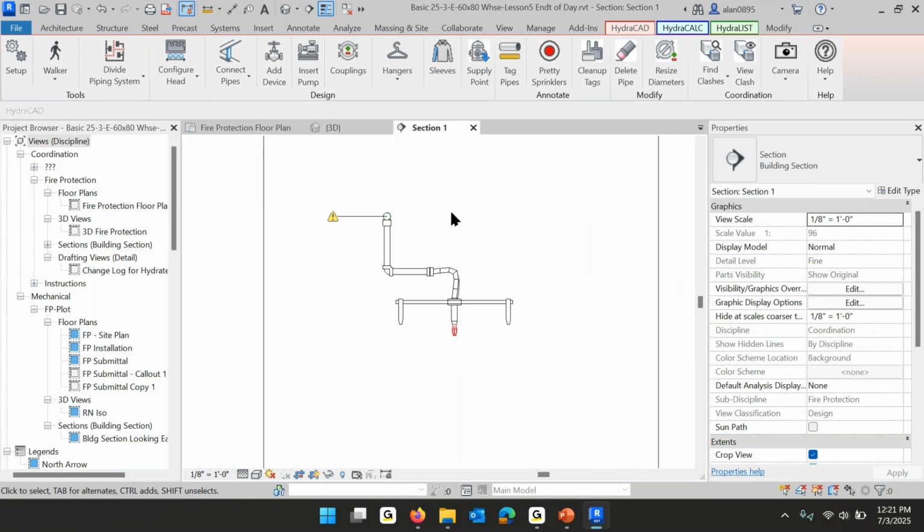Anyone have questions or comments on that before I show you trying to get fancy and make this thing be an elbow? Can you show on the pick 3 points? What is the third point that you pick? The first 2 points define the area that you want to space in, so it's like the range or the scope. How big of a room are we working on? That third point is the actual intersection of two grid lines. That's how it knows to put the heads in the grid center lines. Okay. Yeah.